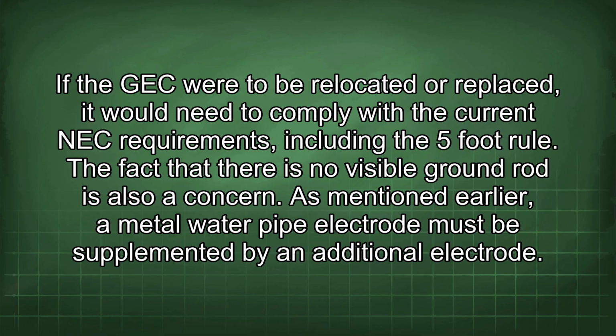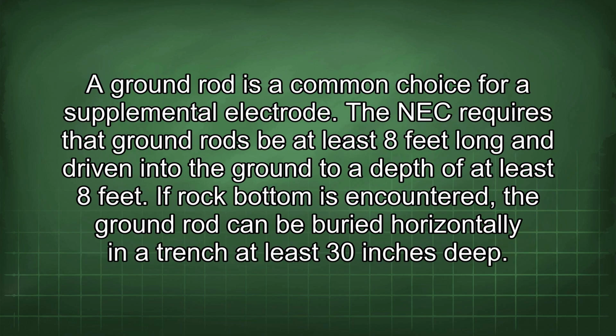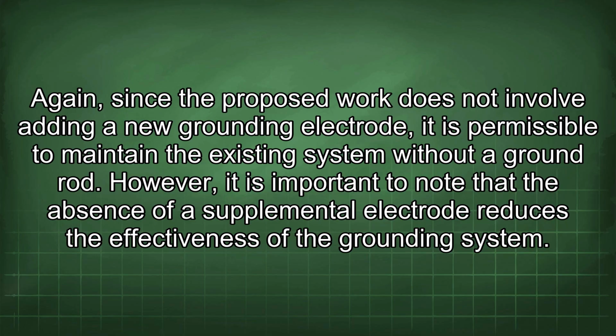As mentioned earlier, a metal water pipe electrode must be supplemented by an additional electrode. A ground rod is a common choice for a supplemental electrode. The NEC requires that ground rods be at least 8 feet long and driven into the ground to a depth of at least 8 feet. If rock bottom is encountered, the ground rod can be buried horizontally in a trench at least 30 inches deep. Again, since the proposed work does not involve adding a new grounding electrode, it is permissible to maintain the existing system without a ground rod. However, it is important to note that the absence of a supplemental electrode reduces the effectiveness of the grounding system.